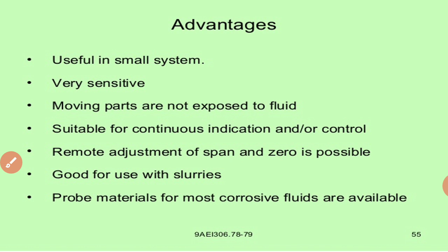Now advantages of using the capacitive level measurement technique. Useful in small systems, and very sensitive. Moving parts are not exposed to fluid. Then suitable for continuous indication and or control. Say in some industries there is a need of continuous indication or continuous control, for example, in petrochemical industries or in furnaces.